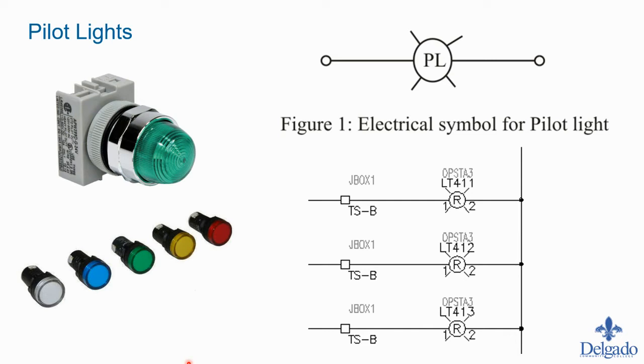Using standard ISA ANSI symbols as much as possible, pilot lights are simply illuminated indicators — basically a light bulb. You can get different color lenses or LEDs. Typical colors are red, green, yellow or amber, blue, and white. Red and green are usually very universal: red indicates something bad or off, and green indicates something good or running. Yellow is typically a warning of some sort.